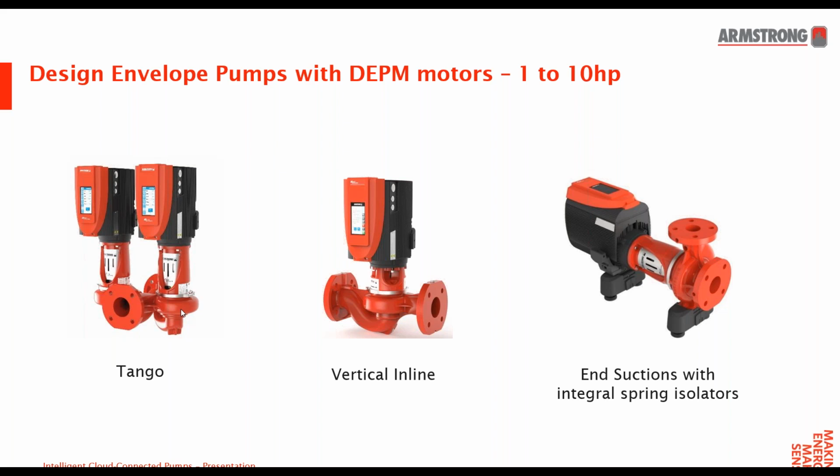Great, thank you, David. Another question, because you were dealing with power, right? What happens if we have an unstable power supply? If the voltage is 360 instead of 460, how does that affect the pump's operation? Okay, that sounds like your typical under voltage issue. We've seen in some installations, especially one where the pumps were installed near a subway line and there was some unstable power, the pumps would have a warning, and they would stop running.